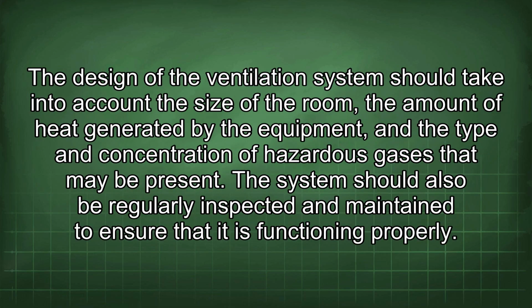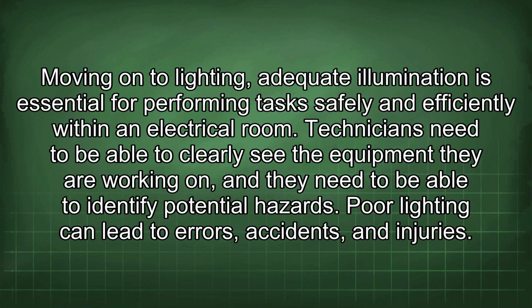The design of the ventilation system should take into account the size of the room, the amount of heat generated by the equipment, and the type and concentration of hazardous gases that may be present. The system should also be regularly inspected and maintained to ensure that it is functioning properly. Moving on to lighting, adequate illumination is essential for performing tasks safely and efficiently within an electrical room. Technicians need to be able to clearly see the equipment they are working on, and they need to be able to identify potential hazards. Poor lighting can lead to errors, accidents, and injuries.